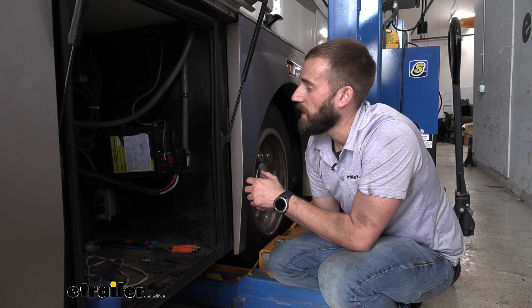As far as installation goes, this can be very simple or pretty challenging. If you're swapping up to a higher amperage converter, you'll also need to swap up your wire gauge, because if the gauge isn't enough, it won't properly support the voltage that goes through there, and you could end up burning the wire out, ruining your breaker, ruining your converter and charger, and also causing an electrical fire.